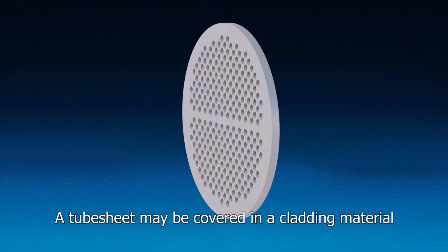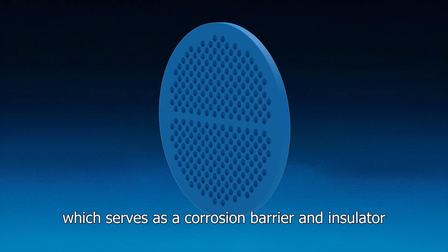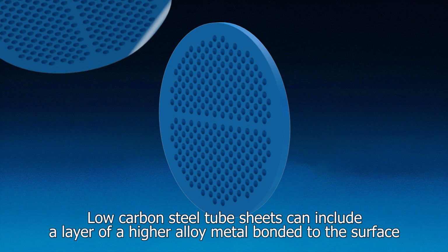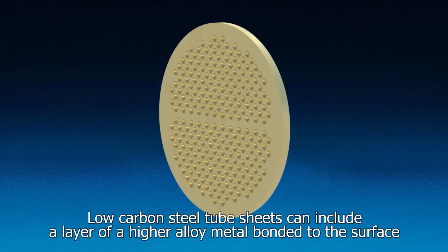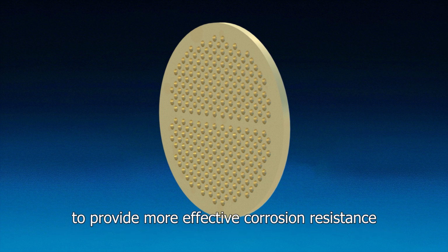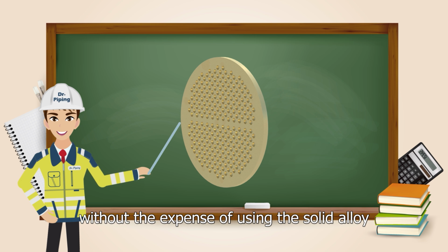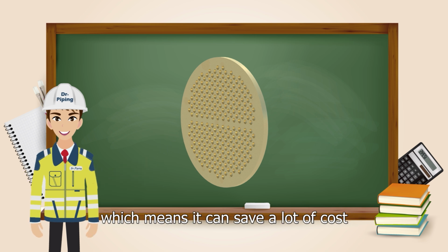A tube sheet may be covered in a cladding material which serves as a corrosion barrier and insulator. Low-carbon steel tube sheets can include a layer of a higher alloy metal bonded to the surface to provide more effective corrosion resistance without the expense of using the solid alloy, which means it can save a lot of cost.